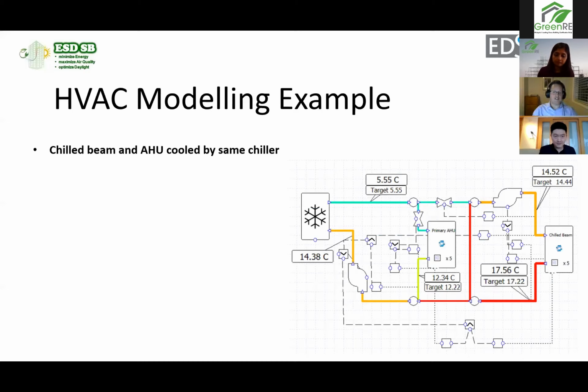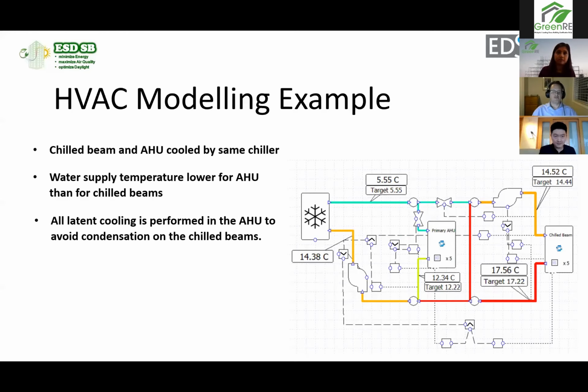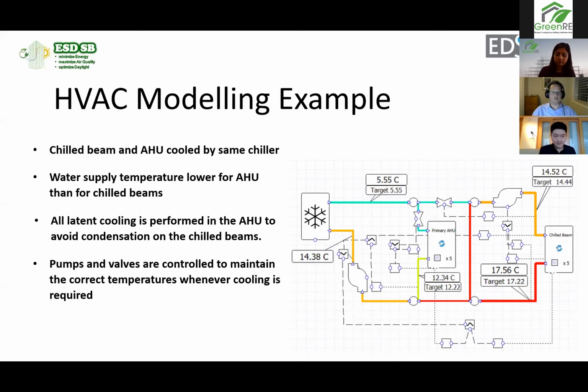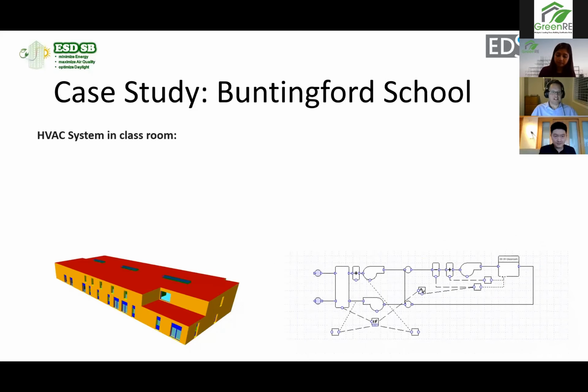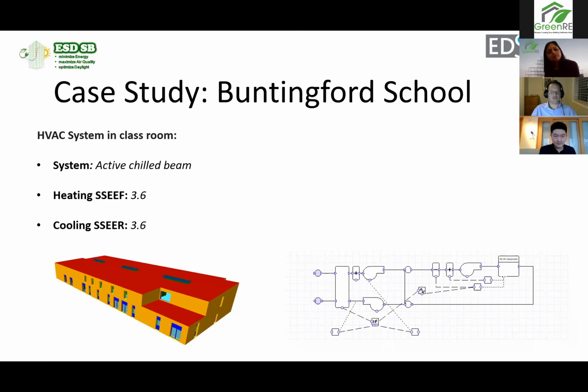This is an example of a system. This is a chilled beam and an air handling unit using the same chiller. The water supply temperature to the AHU is lower than that for the chilled beam. All latent cooling is performed by the AHU to avoid condensation on the chilled beam. The pumps and valves were controlled to maintain the temperature whenever cooling was required. You can see by each of the target values on the screen that we can see on an hourly basis what the temperature is at any given point within the system. In our particular example, the Buntingford School, we did have an active chilled beam. The seasonal efficiency was 3.6 for the heating and for the cooling.